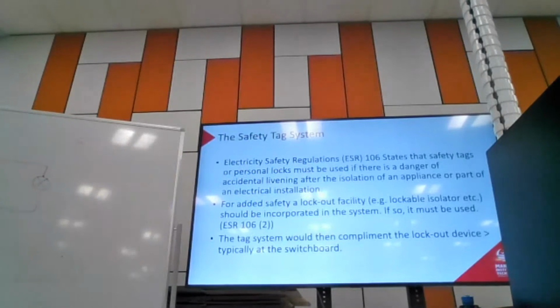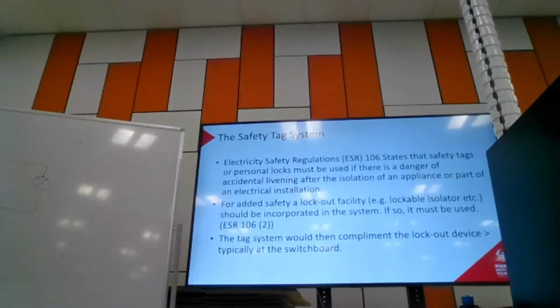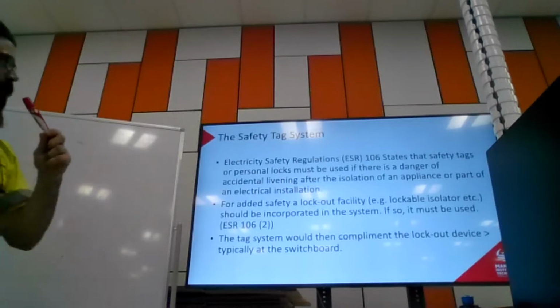So, safety tag system. Electricity safety regulations 106 states that safety tags or personal locks must be used if there is a danger of accidental livening after the isolation of an appliance or part of an electrical installation. For added safety, a lockout facility should be incorporated into the system. If so, it must be used. Electrical safety regulations 106.2. The tag system would then complement the lockout device typically at the switchboard.